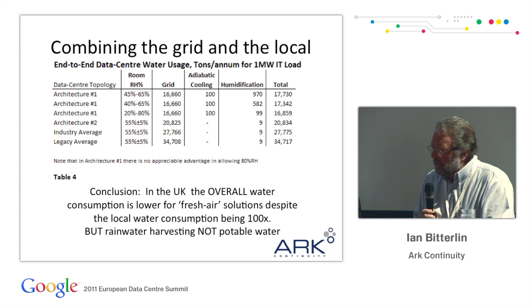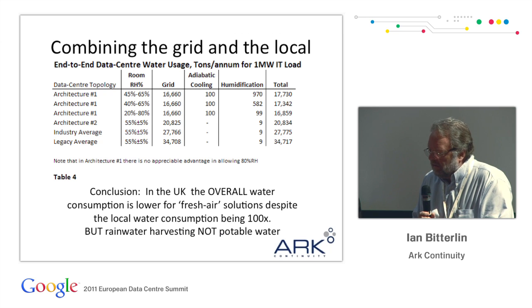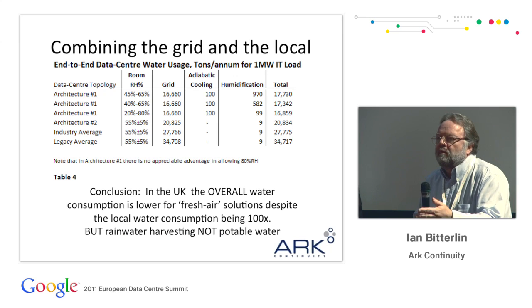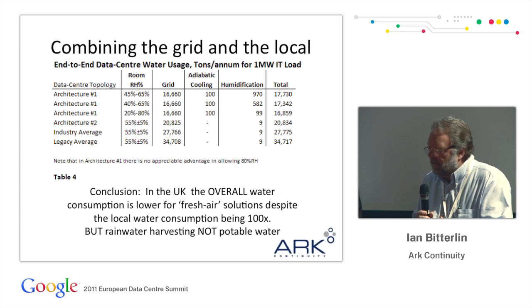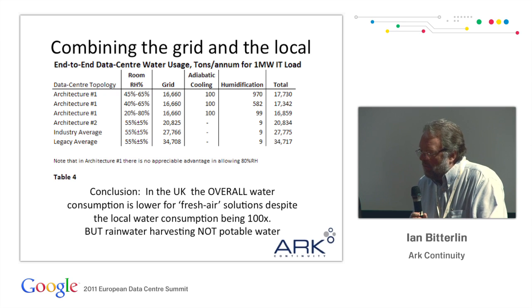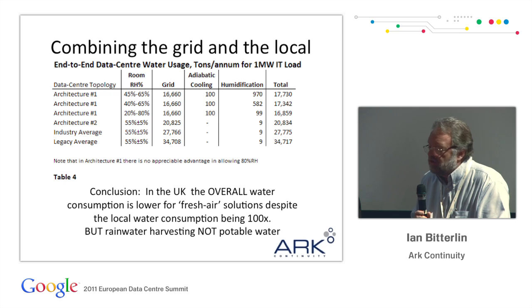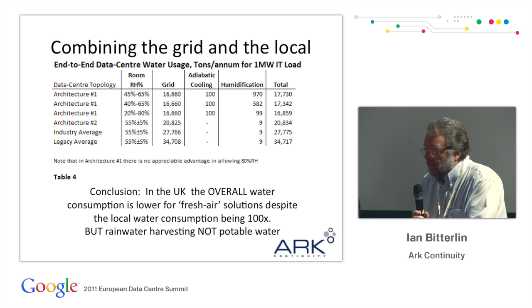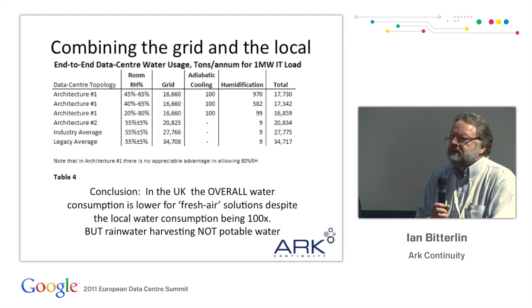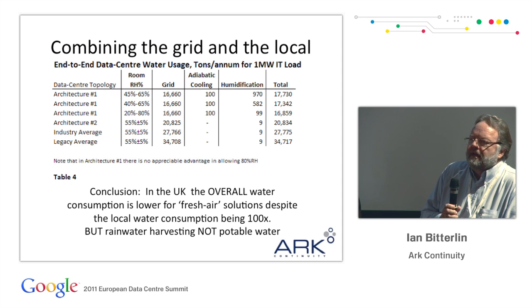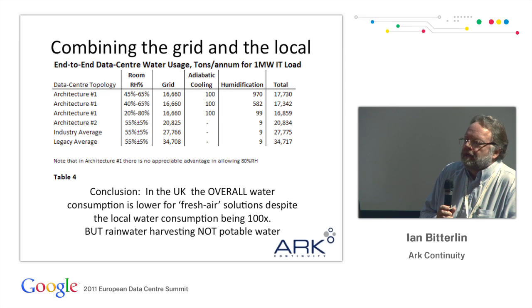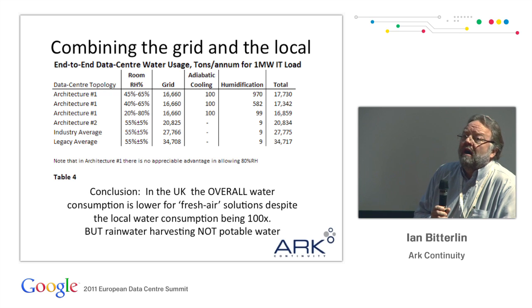So next slide. If you combine the grid and the local, you can see what happens. The architecture number 1 is the fresh air solution, varying expansion of the humidity, from up to the ASHRAE allowable now. And then architecture number 2 is the best practice raised floor, then industry average and legacy average. And you can see that in fact going for a fresh air solution with high water consumption locally does use less water. But, and this is the but, obviously it uses less water as long as you don't use potable water and as long as you've got water free for use in the area where you are. And that's one of our problems.